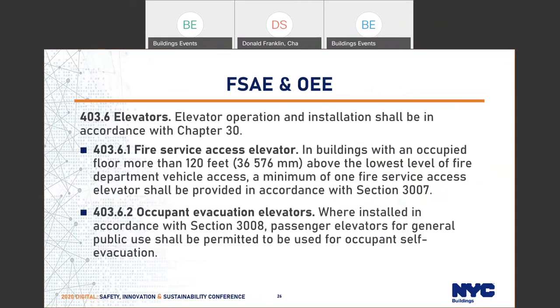The fire service access elevator (FSAE) and occupant evacuation elevator (OEE) went into effect with the 2014 code, but unfortunately the industry is still having difficulty understanding the requirements. The FSAE is often confused with regular fire service Phase 1 and Phase 2, which is incorrect — the FSAE has very unique and numerous requirements. Per BC 403, in high-rise buildings with an occupied floor more than 120 feet above the lowest level, you are required to provide at least one fire service access elevator meeting the requirements of Section 3007.